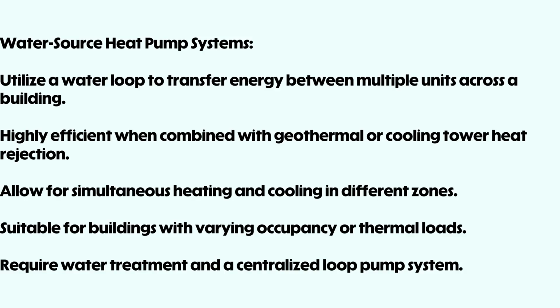A water source heat pump system uses a common water loop throughout the building. Each heat pump extracts or rejects heat to the shared loop, depending on whether it's heating or cooling its zone. This allows simultaneous heating and cooling in different areas, improving comfort and reducing waste.